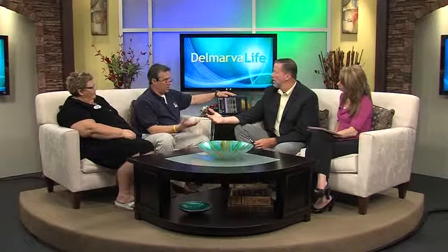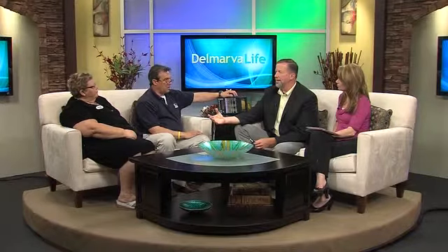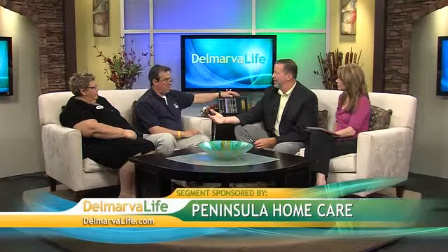The upper extremity is different than the lower extremity, so we have different settings whether it's the knee, ankle, or hand. This is actually an upper extremity triphasic setting. I've had wonderful results with pain — I've had patients who were on methadone that I treated with this unit. It was so effective that we got a portable unit. One lady went to pony penning in Chincoteague, put it on her knee with an ace bandage, spent the whole day there, and never went back on methadone.